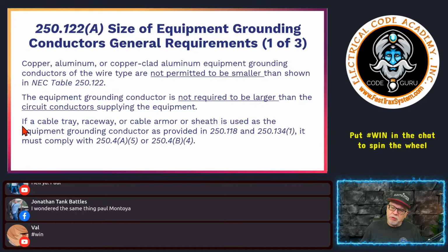All right, so if a cable tray, raceway, or cable armor or sheathing is used as an equipment grounding conductor, okay, which they can if they're listed as such, and there's a lot of raceways that are listed in 250.118, right? And there are cable assemblies like AC cable or that special MC cable, or you could use MC smooth or corrugated, or even an MI type of cable, those type of things would qualify as an equipment ground in 250.118, right? Then it must comply with 250.4(A)(5) and 250.4(B)(4).